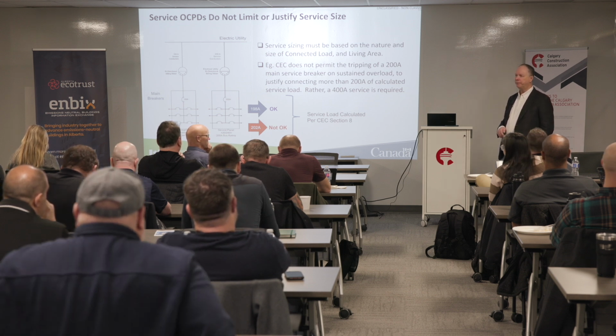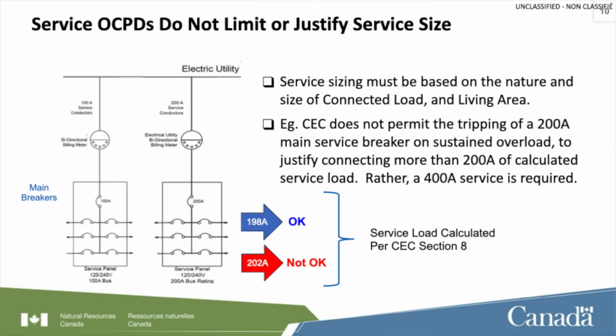Anyway, we talked about how overcurrent protection devices do not limit or justify the service size. So you can only put 100 amps on a 100 amp service, only 200 amps on a 200 amp service. If you've got your Bitcoin mining operation or hydroponics going in the basement, you may need to upgrade your service. We had 2 furnaces doing 60 amps each - it's right there, it was 100 amps. Those are some big furnaces.